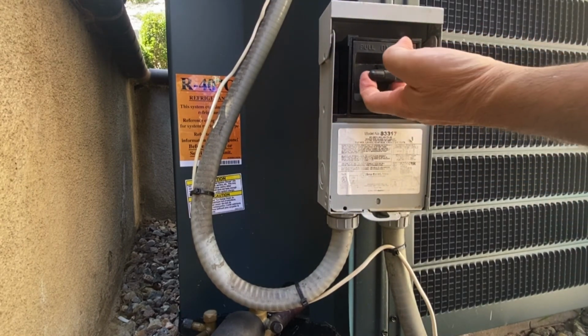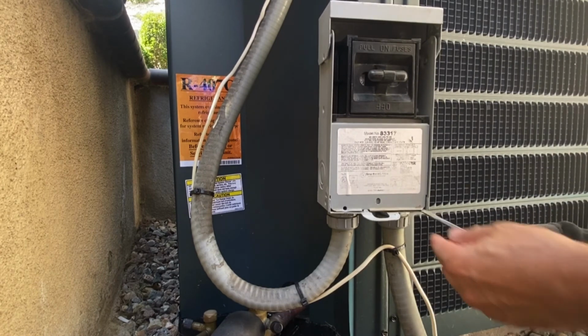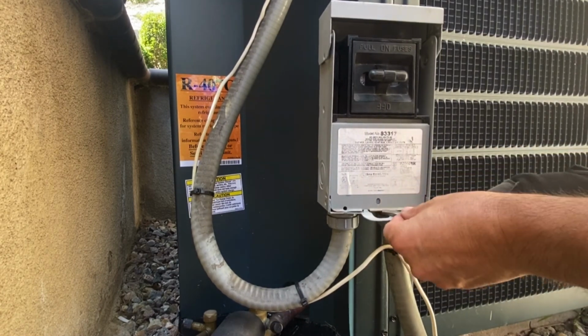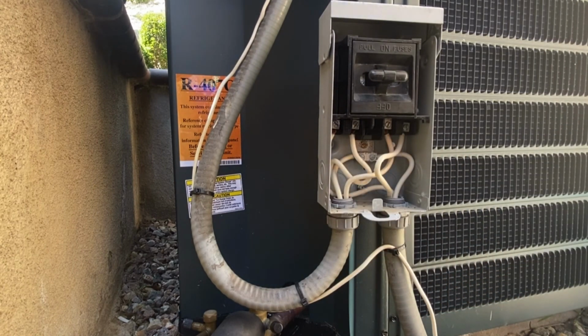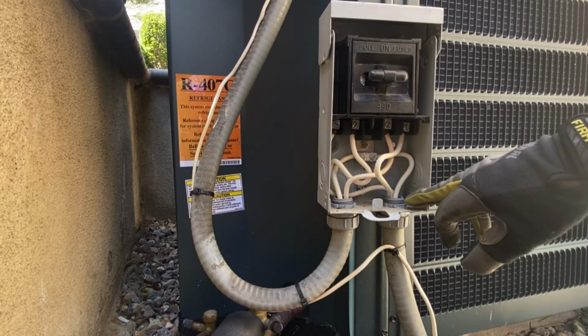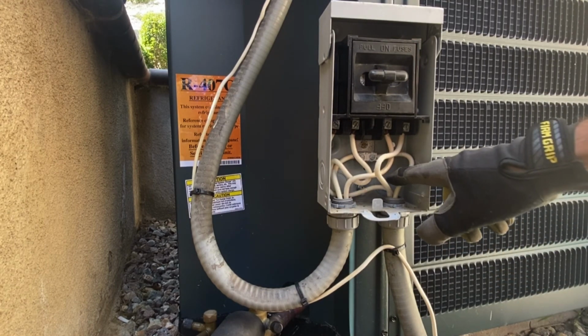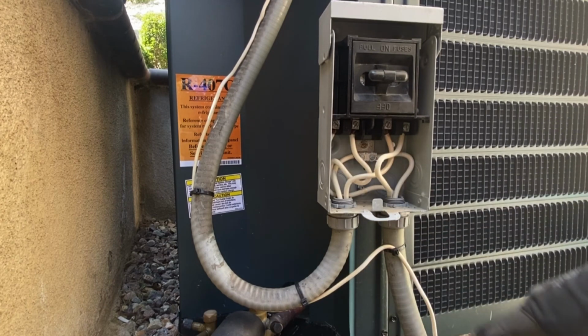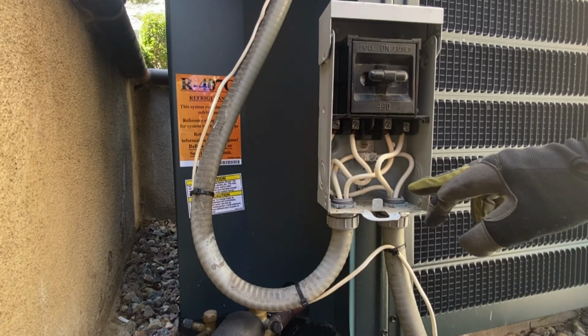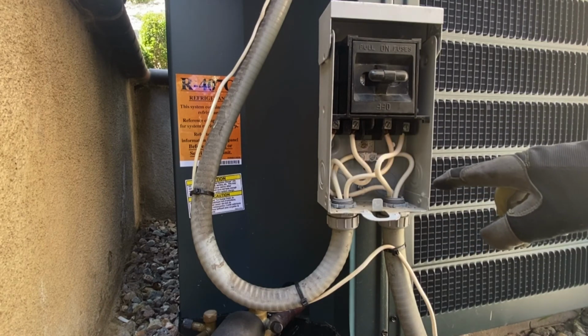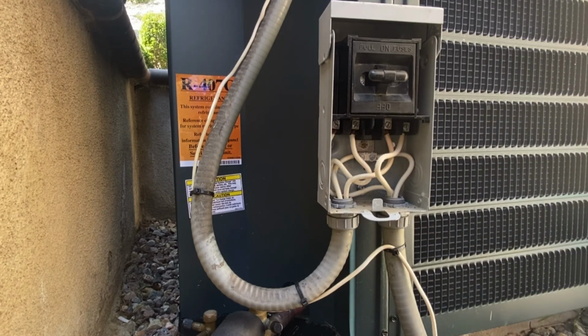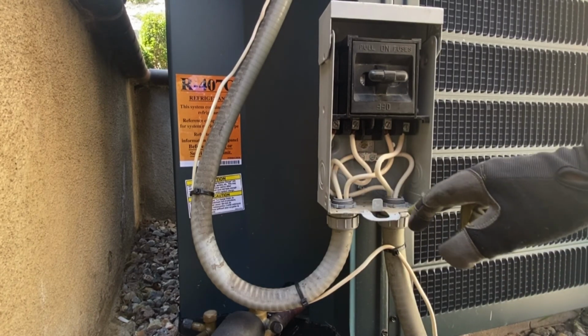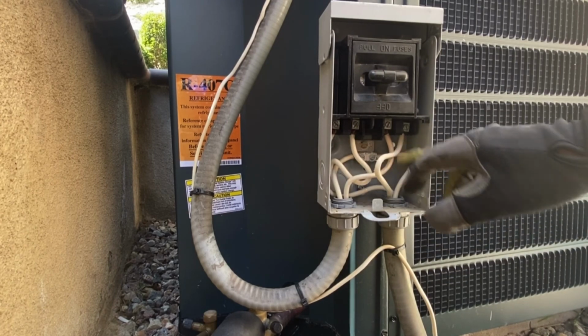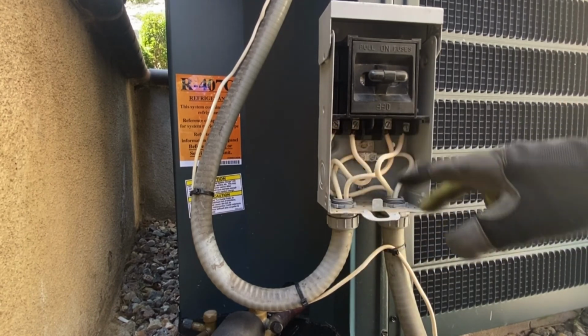See my fuses and my pullout for my fuses. Get in here to look at the electrical. It's usually a little tougher to get off, to keep people out. Look in here, we can see my two high voltage wires coming in from my circuit breaker panel, L1, L2, and also my ground wire. None of these are properly color coded. That's a problem, but it is what it is. So all the more reason I have to follow these wires so I can see which ones are going where.